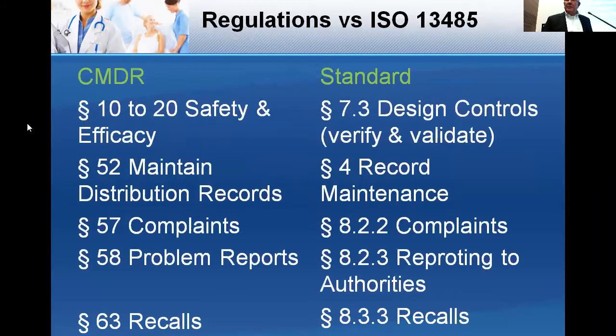Sections 10 to 20 of the Canadian Medical Device Regulations deal with safety and efficacy, which can be directly linked to the design controls in the standard. Section 52 of the Canadian regs talks about distribution records, which is section 4 of your standard. Complaints is section 57 of the Canadian regs, which is 822 of the standard. Problem reports, or mandatory problem reports, is section 58 of the regulations and section 823 of the standard. And recalls is section 63 of the regulations, which is section 833 of the standard.